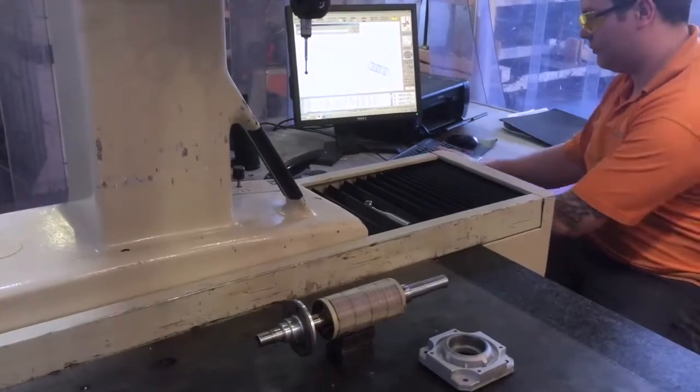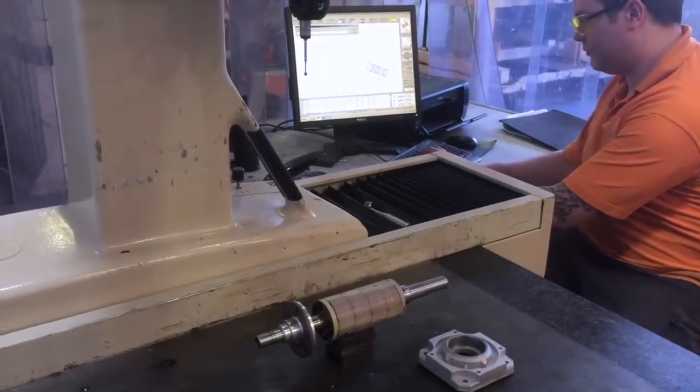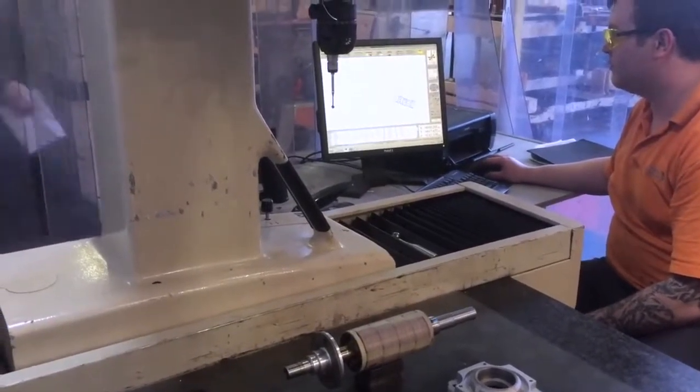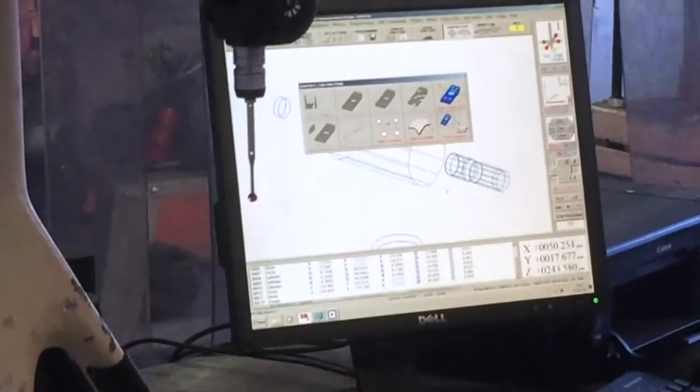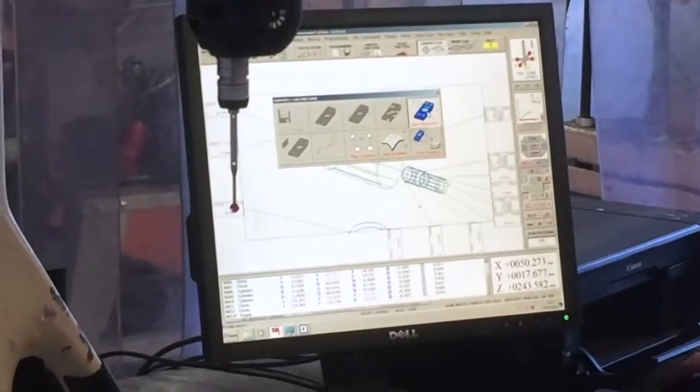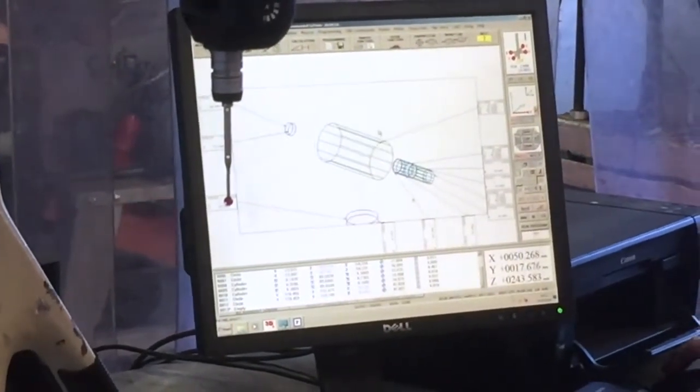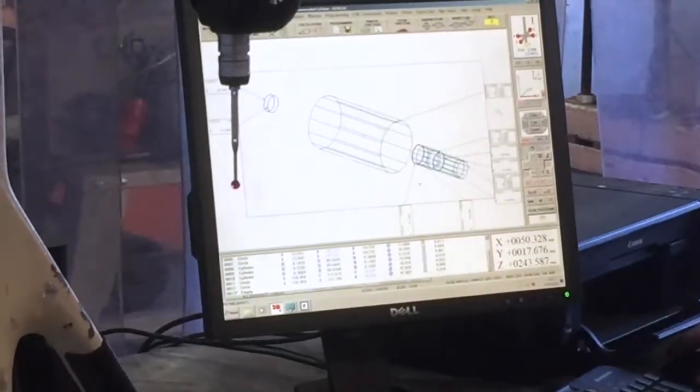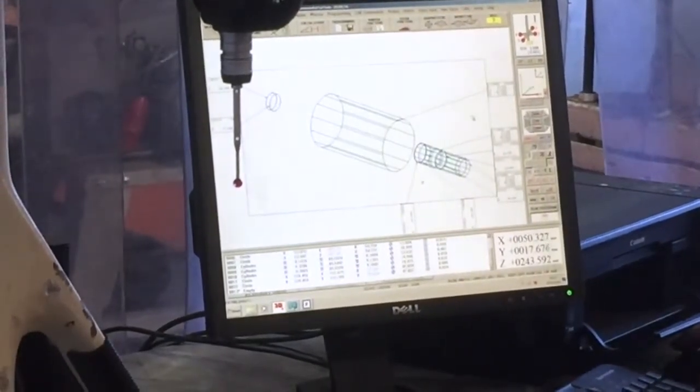The rotor will also be measured for the bearing journals and also for the straightness of the shaft using the coordinate measuring machine. You can see on the screen here where all the measurements have been taken and everything with this rotor is fine. It is straight, the run out is negligible or within tolerance, which will be 0.05mm for this motor.